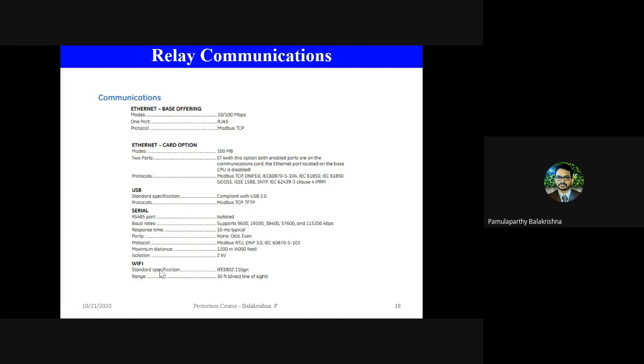Okay, no problem. In the current digital era, as everyone knows, mobile apps are the way people manage different things. Similarly for a relay, you can have a mobile app that you install on a mobile or an iPad. Once the relay is connected to Wi-Fi, and your mobile or iPad is connected to the same Wi-Fi, you connect to the relay and get all the information of the relay. Without going near the relay or the machine, within the range of Wi-Fi you get all the information on your mobile. Even if there is any problem with the equipment, or any trip function or protection function has tripped, you immediately get a message in the app that something has happened in the field, and the operator can quickly take action. For that purpose, modern digital relays also support Wi-Fi.